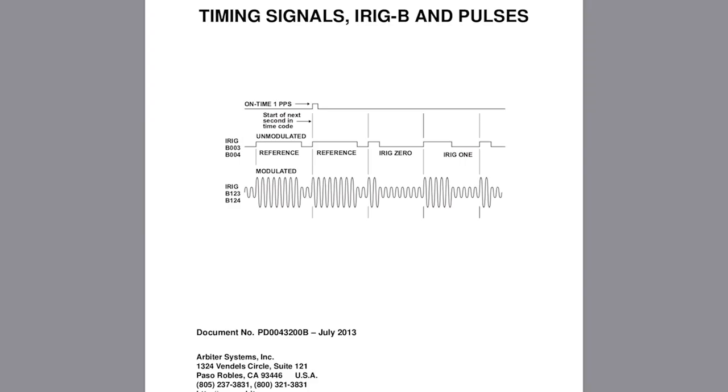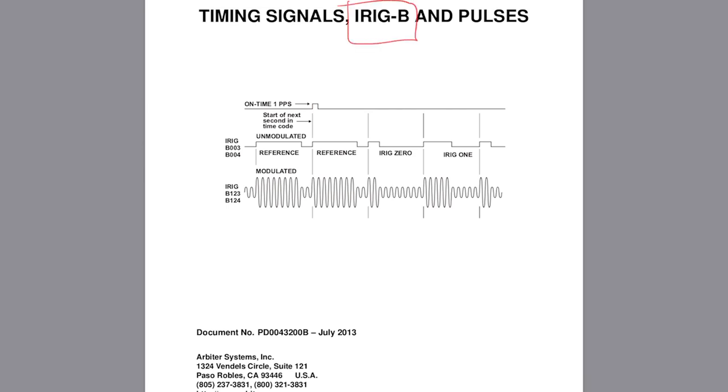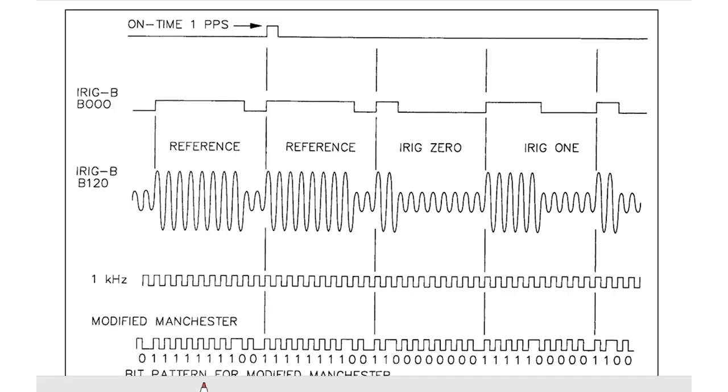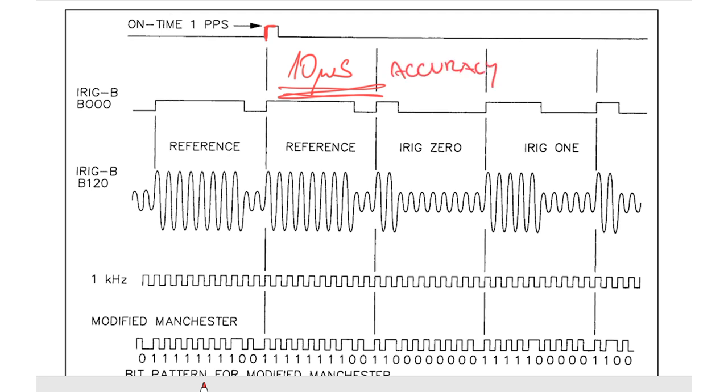The signal what we will receive to our display is called IRIG-B. So the signal is sine wave with amplitude modulation. It can have either high peaks or low peaks. And today we will focus on how to get a one PPS signal from the analog wave. And we need to detect it precisely with accuracy within 10 microseconds.